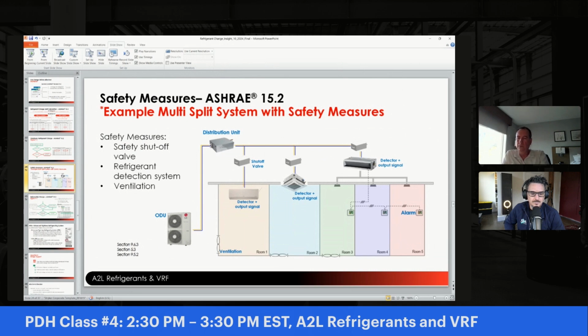Let's see, the detectors, is there one in each room, it looks like, is that right? Yeah, for a home, these will be built into the indoor units themselves. Oh, they're built into the indoor units, so you don't have to worry. Got it. Nice. Yeah, LG actually has a refrigerant leak sensor available globally, but we've never brought it over here. And I think this is better that it's all built in anyway, and you've got one less thing hanging out on the wall or connected somewhere.